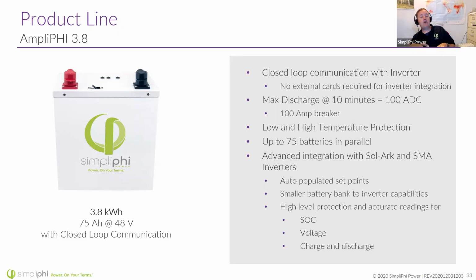The battery can also transmit data like its state of charge, voltage, and charge and discharge rate to the piece of equipment, so you're getting a much higher level accurate reading when the battery is telling the equipment what to do. Another thing is that you can have a smaller battery bank relative to the inverter capabilities. Keep that phrase in your head for a second, because we're going to come back to that.